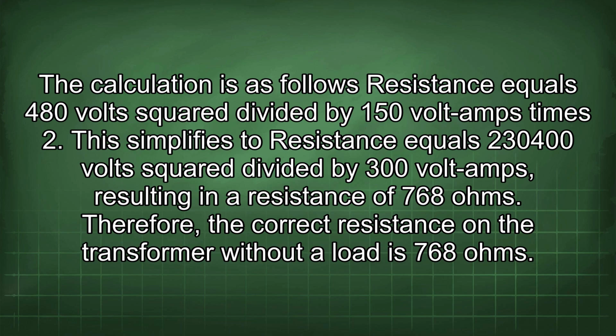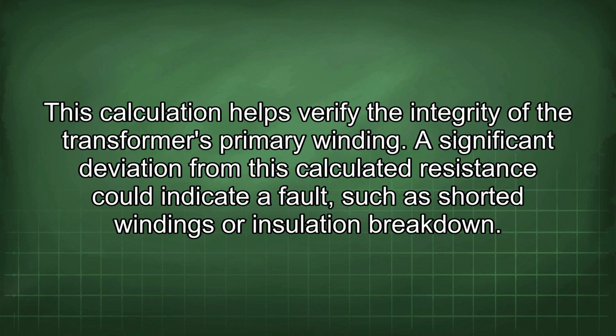This simplifies to resistance equals 230,400 volts squared divided by 300 volt amps, resulting in a resistance of 768 ohms. Therefore, the correct resistance on the transformer without a load is 768 ohms. This calculation helps verify the integrity of the transformer's primary winding. A significant deviation from this calculated resistance could indicate a fault, such as shorted windings or insulation breakdown.